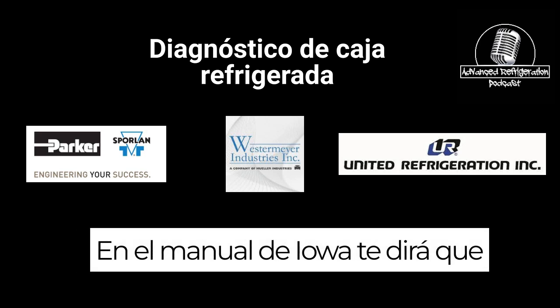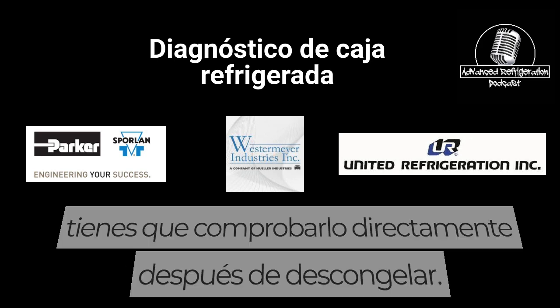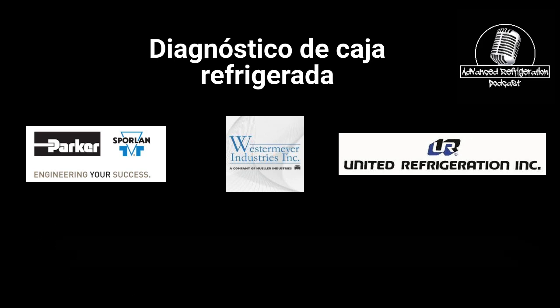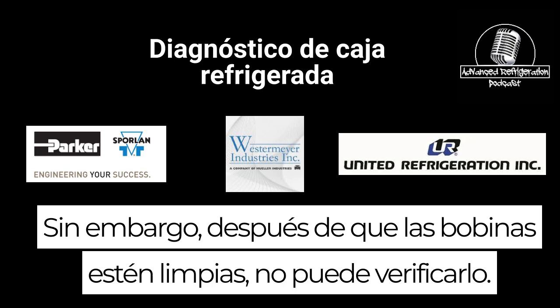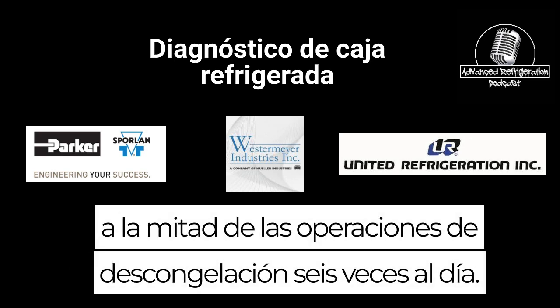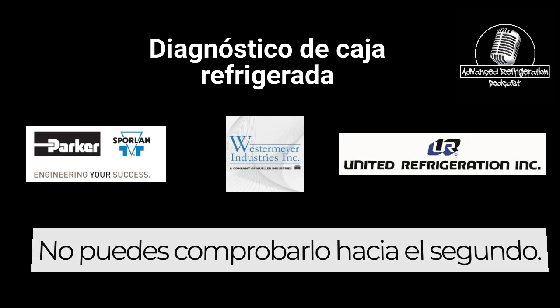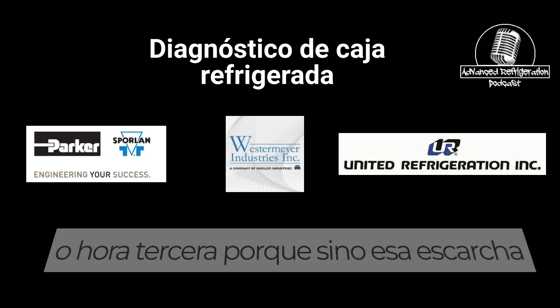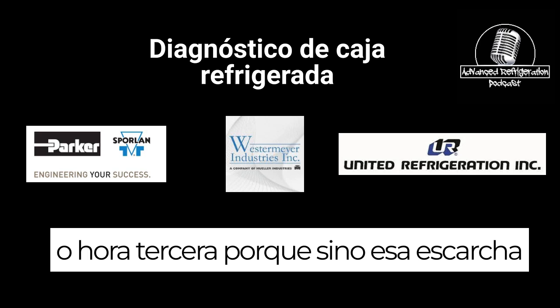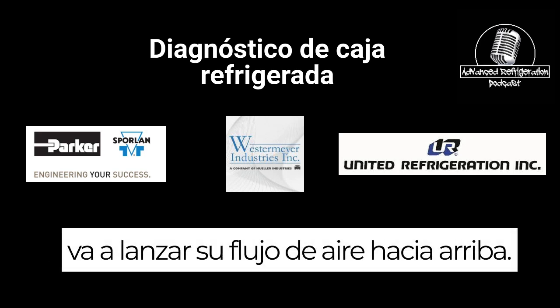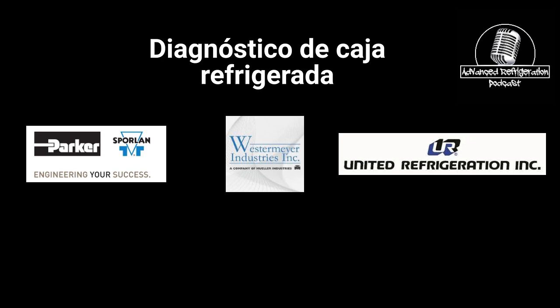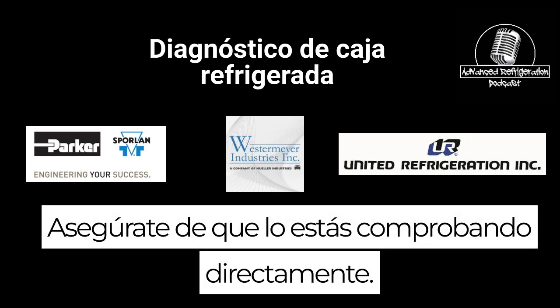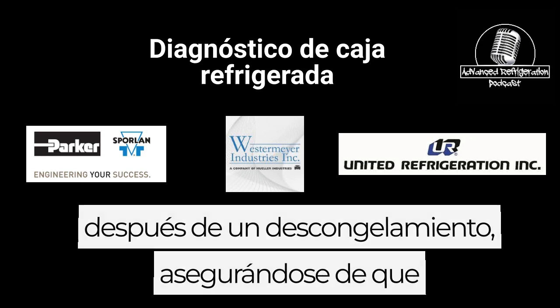In the IOM manual, it'll tell you that you have to check it directly after defrost, after the coils are clear. You can't check it midway through operation. So if the defrost is 6 times a day, you can't check it towards the second or third hour, because otherwise that frost is going to restrict and throw your airflow off. Make sure that you are checking it directly after a defrost.